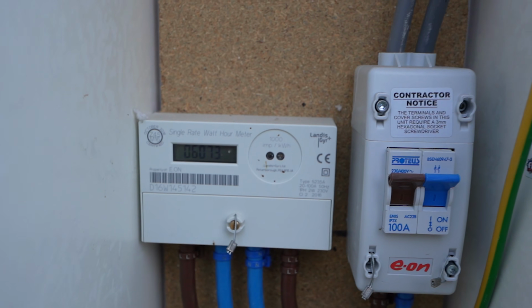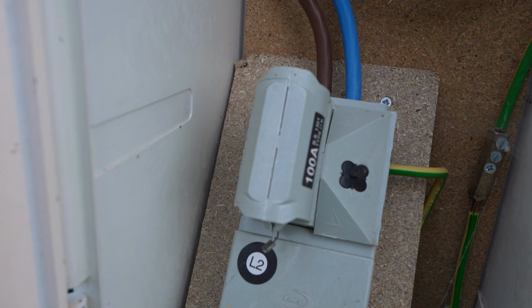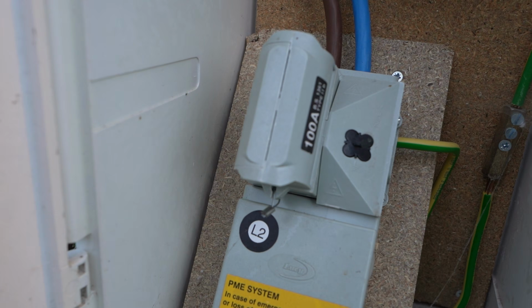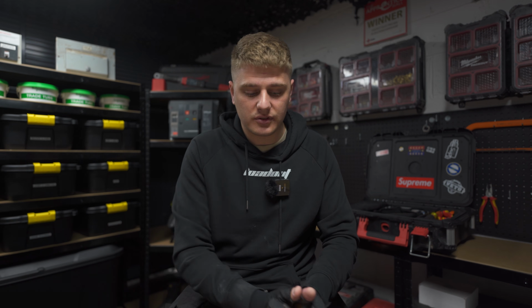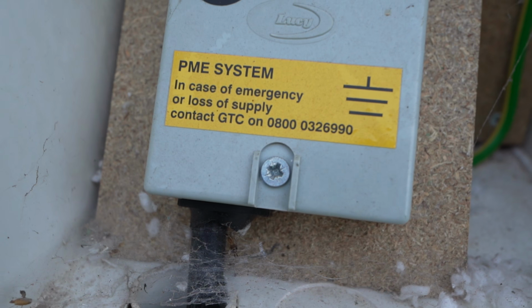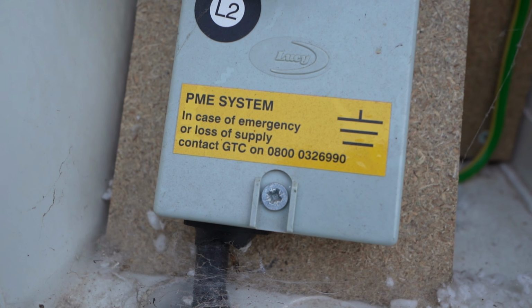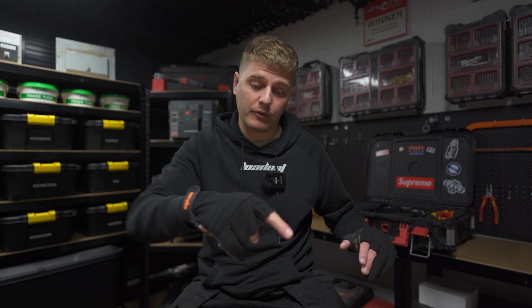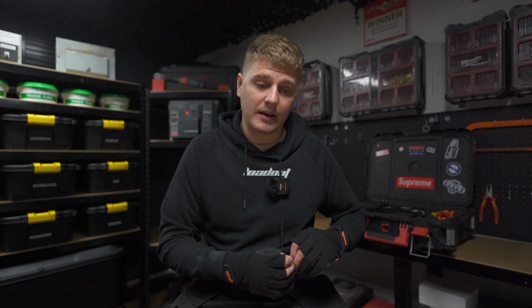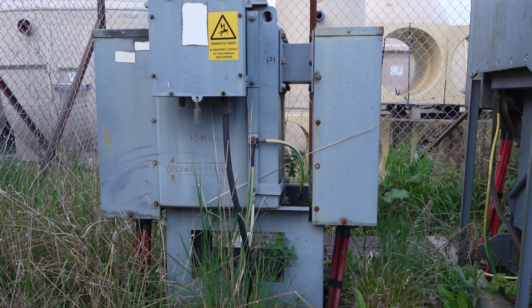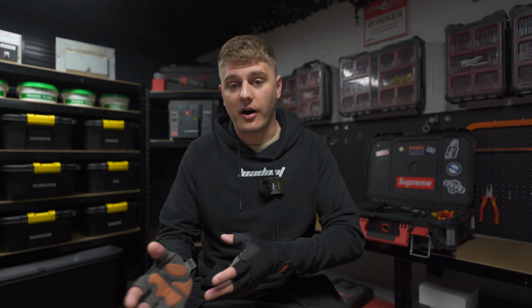Now, diverted neutral currents are basically where the neutral current of the installation is taking an alternative path because it has to, or it has the ability to. So for instance, if you lose the protective earth neutral conductor to a house, then that neutral current can have nowhere to flow, but there's actually a parallel path through the main equipotential bond onto the water or the gas, which then runs through the ground. So it can take that path through the bond, down the pipe, and actually end up back at the supply transformer or earth basically. And that's the path it's going to take, just because that's how electricity works.